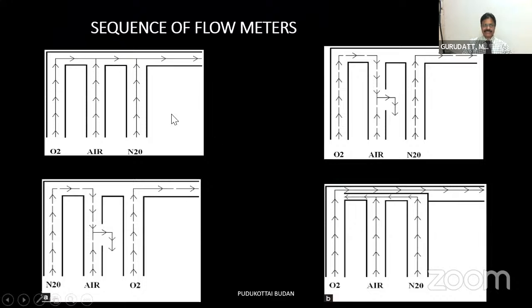One more question you will be asked is about the sequence of flow meters. Again, this is very important. Nowadays, machine standards say that oxygen should always be the most downstream of all the gases. That is the Eger's sequence of flow meters. Suppose oxygen is upstream and nitrous oxide is downstream. I'm showing you this in the first diagram. If there is a break in the air flow meter, then the oxygen will start flowing out, the patient may get more nitrous oxide, and a hypoxic mixture can be delivered. Suppose oxygen is downstream. Then even if there is a break here, nitrous oxide will flow out, but the patient will still get enough oxygen, and it is going to prevent any hypoxic mixture being delivered. So the sequence of flow meters is again an important exam question you will be asked about.